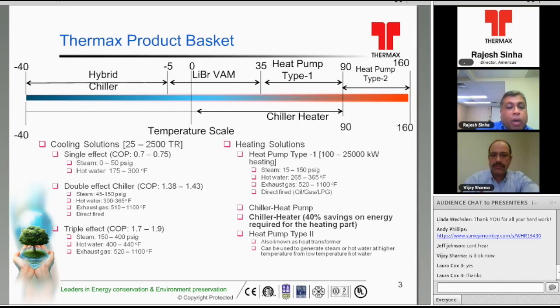And then we have the chiller heat pump, which can simultaneously handle chilled water requirements as well as heating hot water requirements, with a huge saving on input heat energy. And we will see how in the subsequent slides when we discuss the product. The last type of product which we have is the heat pump type 2, which is also known as the heat transformer. Herein, we can actually use low-grade waste heat to generate steam. That's the heat transformer.